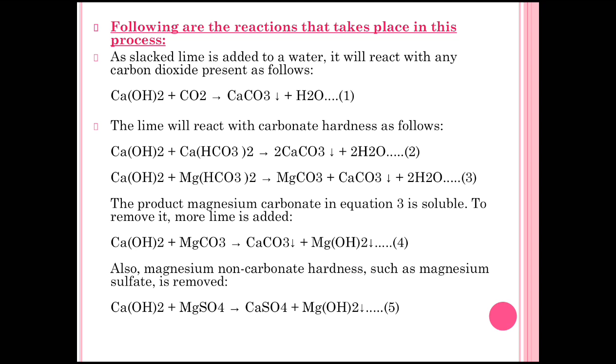The following reactions occur in this process. First, when slack lime is added to water it reacts with any carbon dioxide present: Ca(OH)₂ + CO₂ → CaCO₃ (precipitate) + H₂O. The lime then reacts with carbonate hardness: when lime reacts with calcium bicarbonate, calcium carbonate precipitate settles down. When lime is added to magnesium bicarbonate, magnesium carbonate precipitate plus calcium carbonate precipitate settle down, and after filtration the precipitate is removed and water becomes soft.